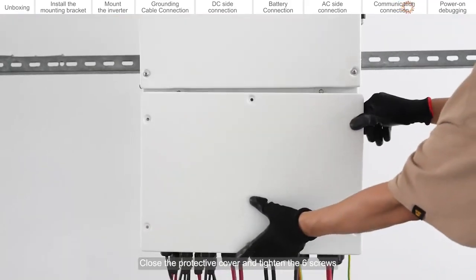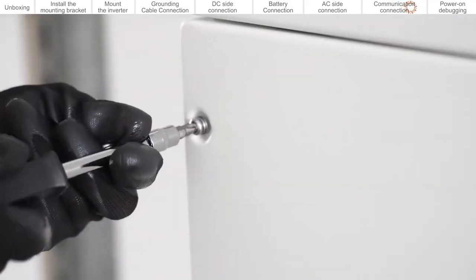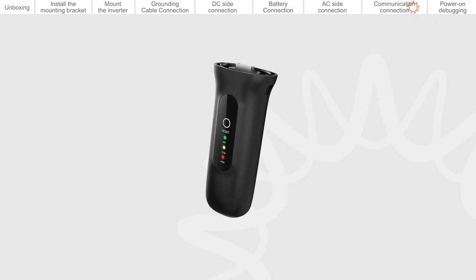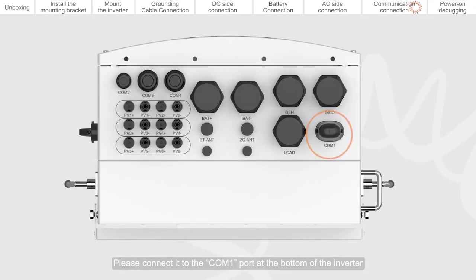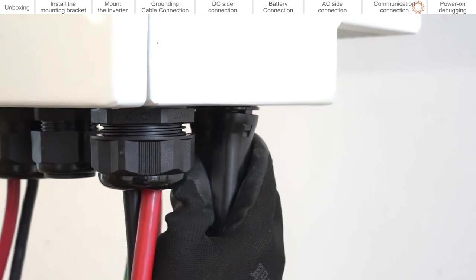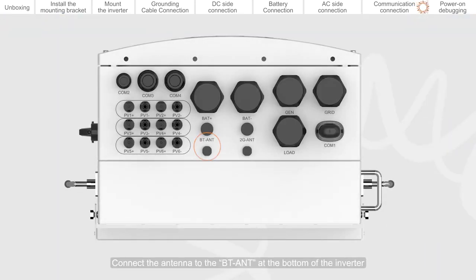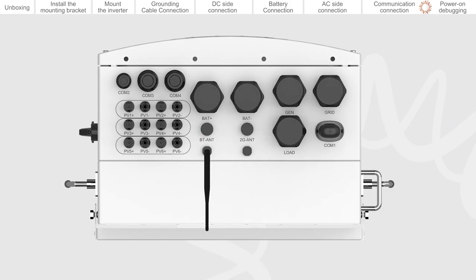Close the protective cover and tighten the 6 screws. If you choose a Solis data logger, please connect it to the COM1 port at the bottom of the inverter. Connect the antenna to the BT ant at the bottom of the inverter.